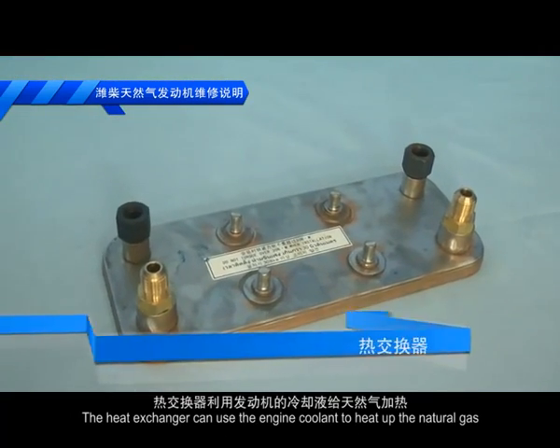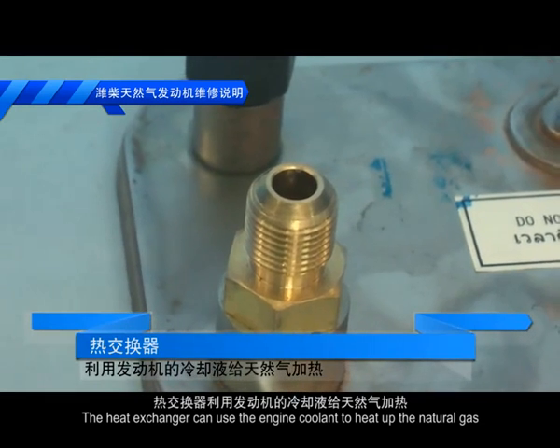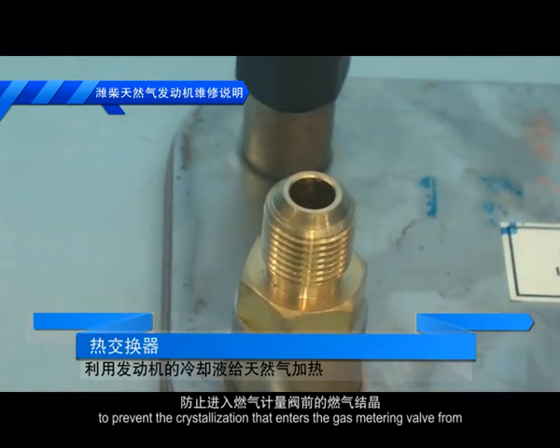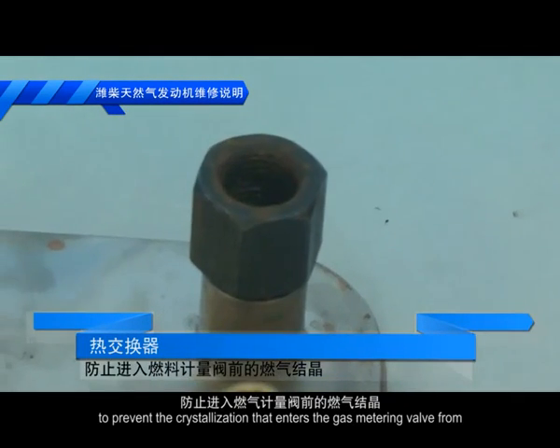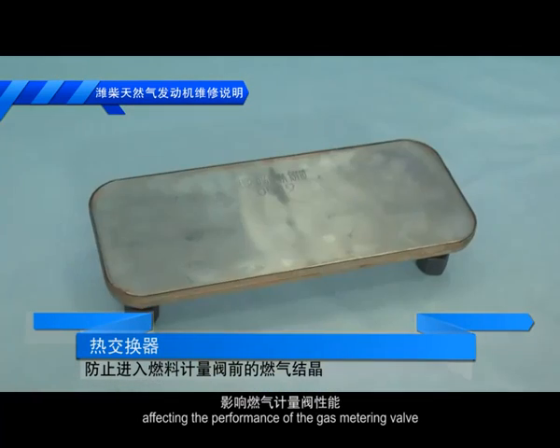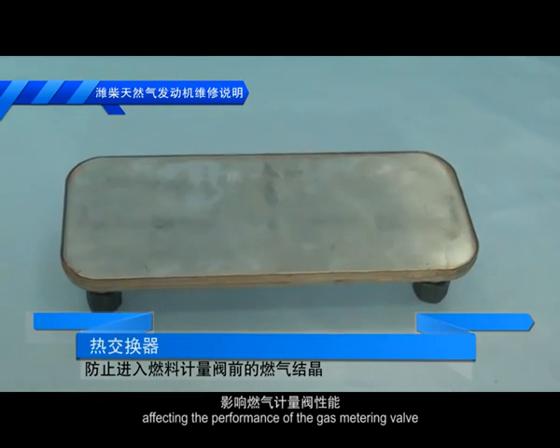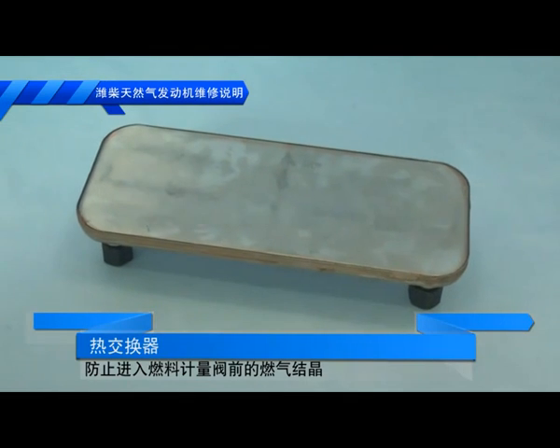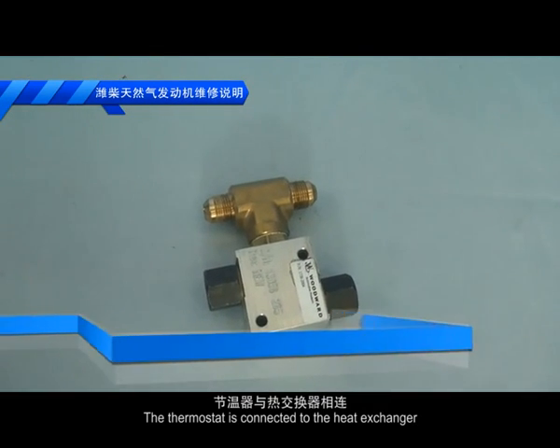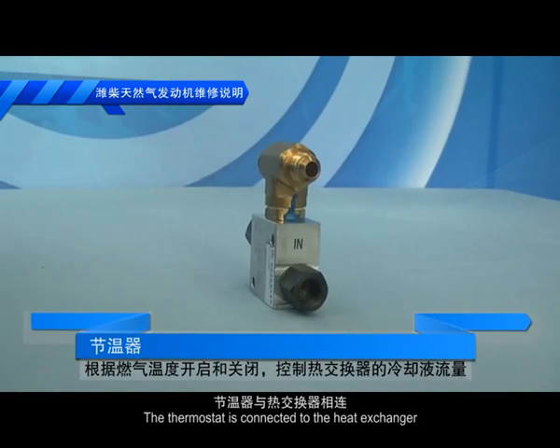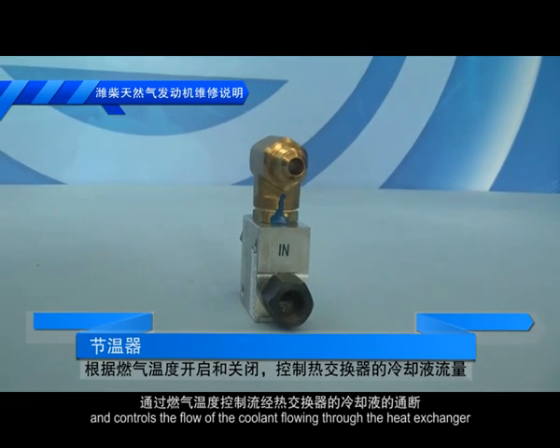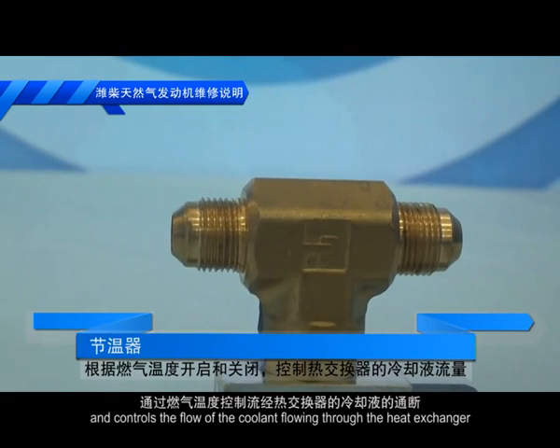The heat exchanger can use the engine coolant to heat up the natural gas to prevent the crystallization that enters the gas metering valve from affecting the performance of the gas metering valve. The thermostat is connected to the heat exchanger and controls the flow of the coolant flowing through the heat exchanger.